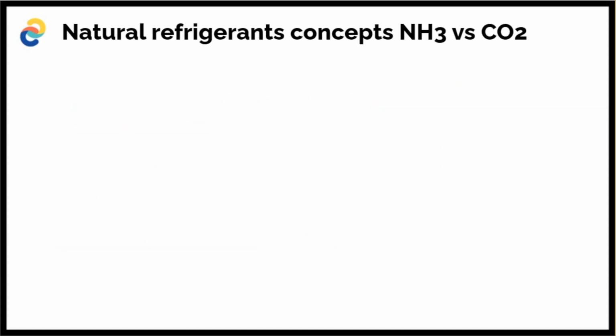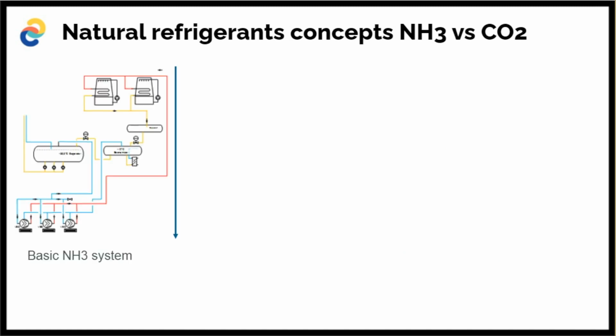Now, what we normally use on these concepts, so we have the coolers looked at, we have the compressors looked at. Let's look at the whole thing at the moment, basic concepts. We have here the basic NH3 system. It's a pump system. It's not with direct expansion, but it's still a pump system. That's always the safest solution there is. It's the cheapest solution. It's the safest solution in terms of it's simple, reliable, energy efficient. However, there are circumstances that customers are not so happy with the amount of ammonia in it. There can be quite a lot of ammonia in it, and of course with the DX systems that could be reduced, but sometimes they don't want to have any ammonia in the cold store itself.